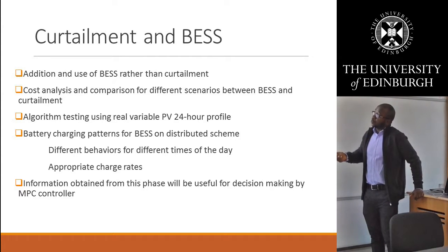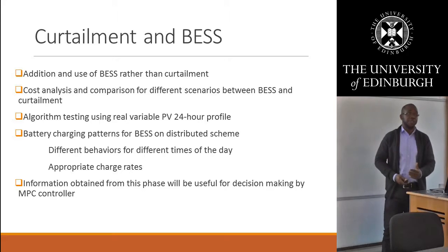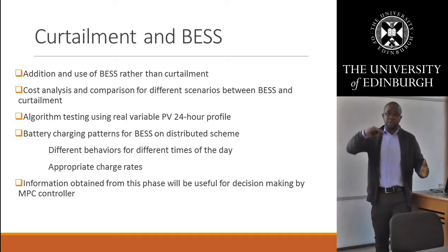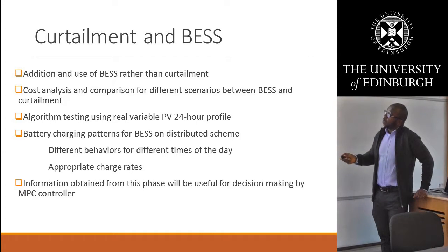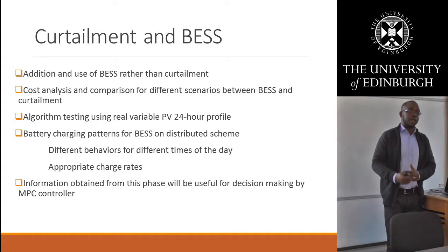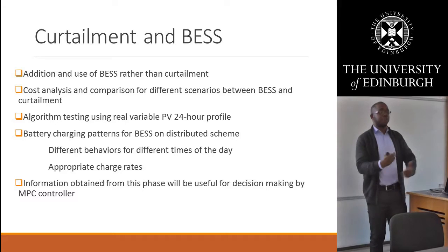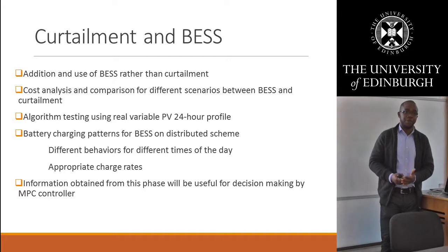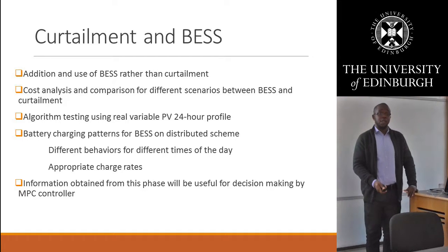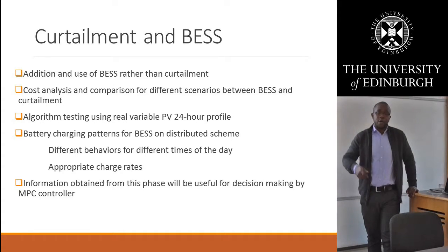And then this is going to have some challenges as well, because PV generation is quite intermittent, and it's not as smooth as it is. And so while adding BESS currently on a real model, the challenges we started seeing are stuff like the batteries. The batteries should come in when we have high production of PVs, but then, depending on the charging rate of the batteries, they could actually get fully charged, and then there's still PV power being produced.